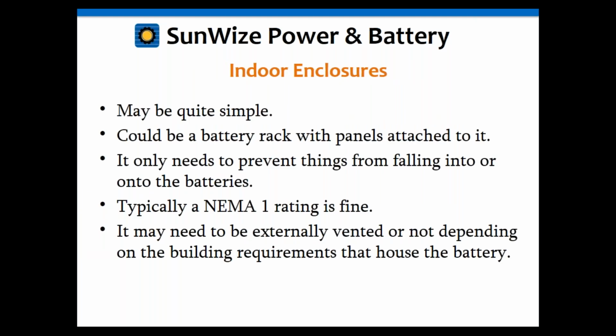Indoor enclosures can be quite simple actually. Again, you're just looking for stuff to fall on top of it or keep people from putting their hands in there. It could be something as simple as, when it comes to batteries, just putting panels on a battery rack. I've seen bolted plexiglass panels around and over top of a battery rack, with the rack pushed up against the wall so the back is covered by the wall. You don't have to have anything underneath, and then on the sides, top, and front they just put some panels over it, and that could be considered adequate—again, only to prevent things from falling into it or on it. So if that's the case, a NEMA 1 can be fine.